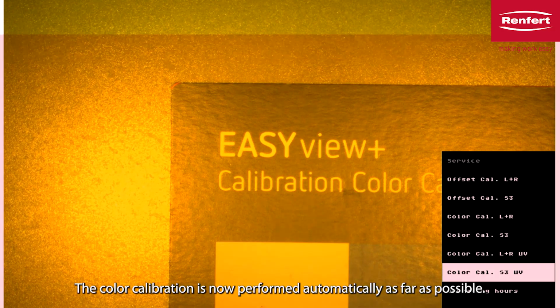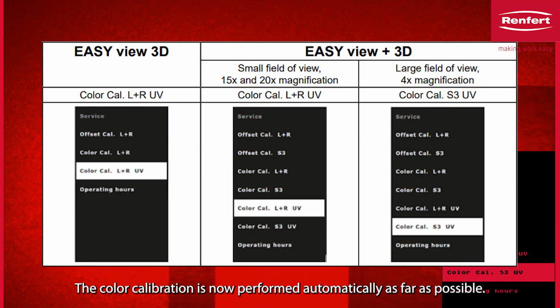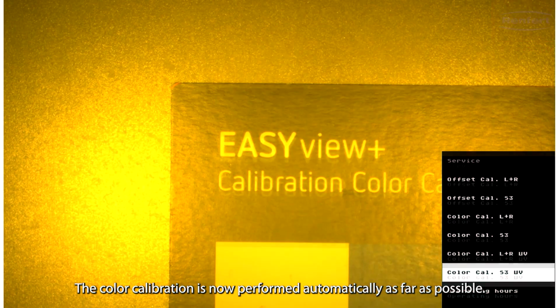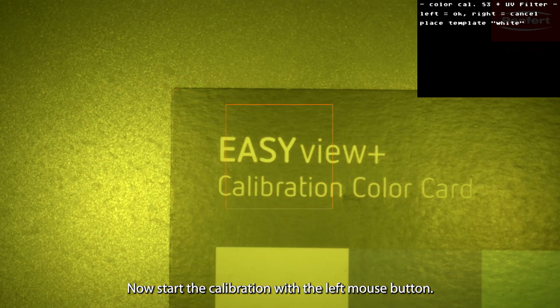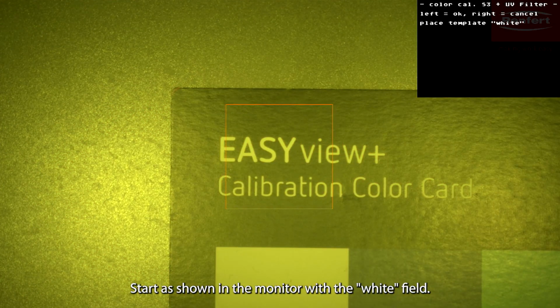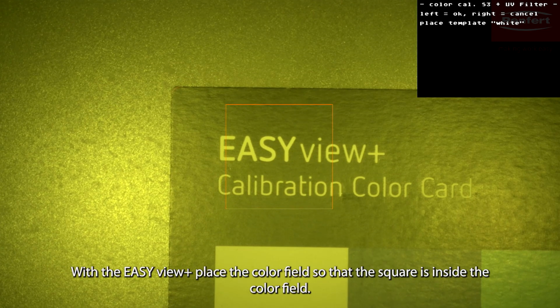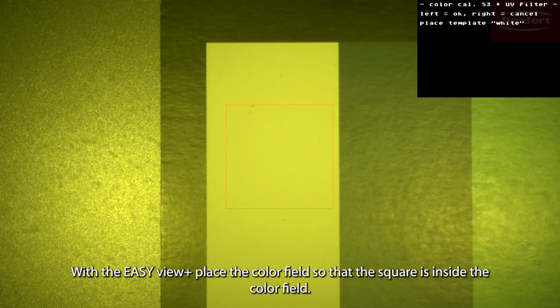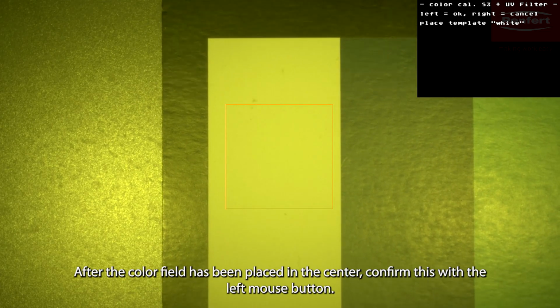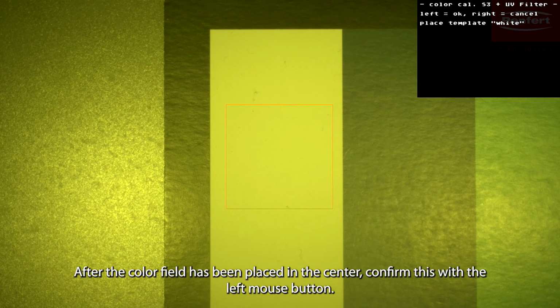With the EasyView Plus, the calibration must be performed separately for the 4 times and the 15 times and 20 times magnifications. Now start the calibration with the left mouse button. Start is shown in the monitor with the white field. With the EasyView Plus, place the color field so that the square is inside the color field. After the color field has been placed in the center, confirm this with the left mouse button.